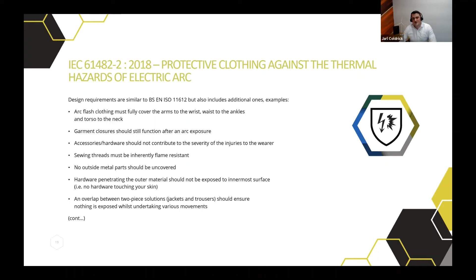Garment closure should still function after an arc exposure, which is essential, especially when you need to take off the garment quickly after an arc flash has occurred. Accessories and hardware should not contribute to the severity of injuries to the wearer, so studs or any exposed metal parts should not be touching the skin. It's also important that there's an overlap between the jacket and trouser on a two-piece solution, ensuring nothing is exposed whilst undertaking various movements.